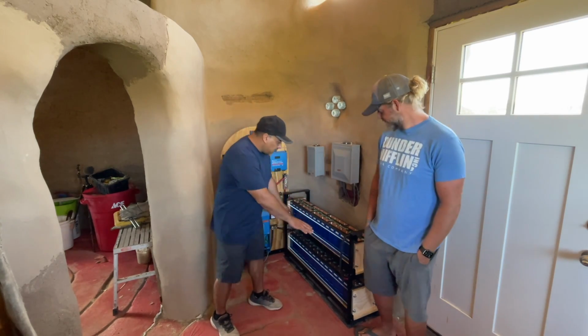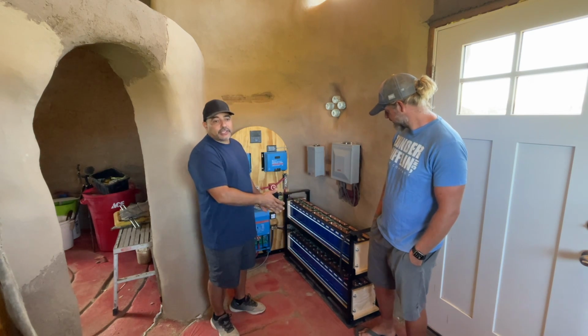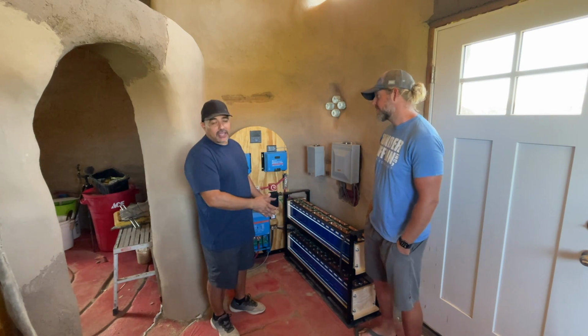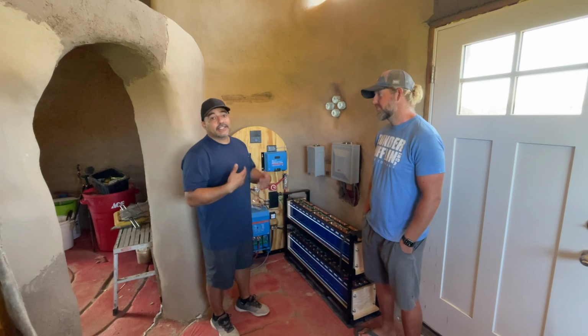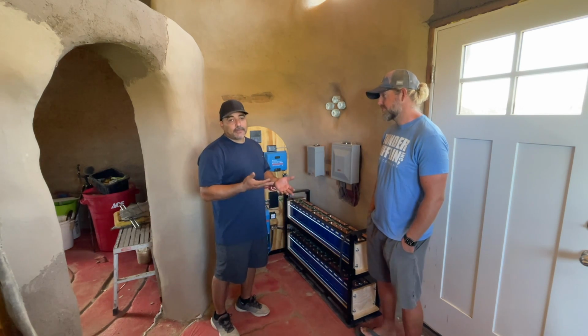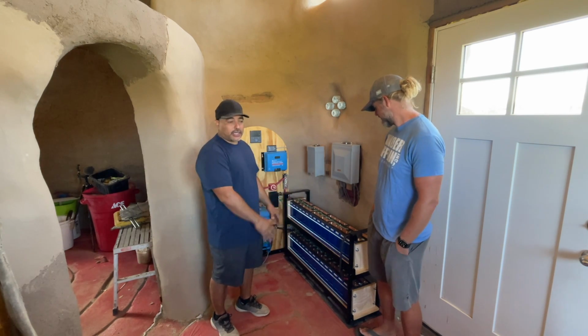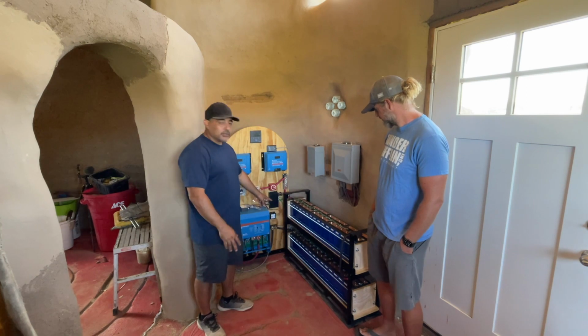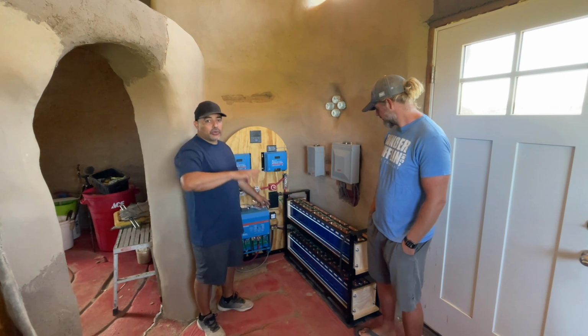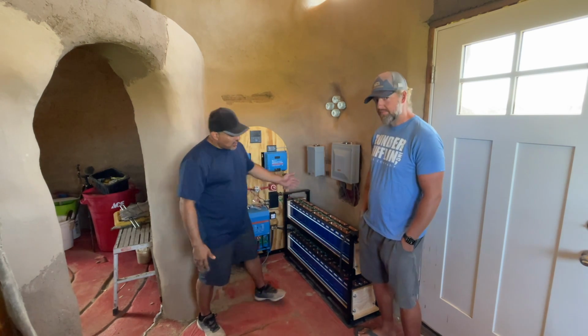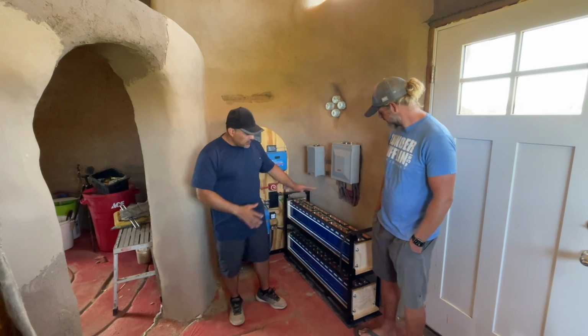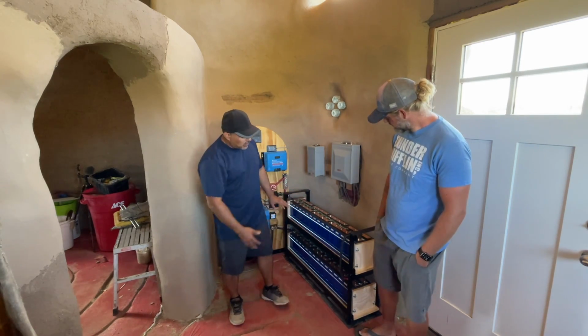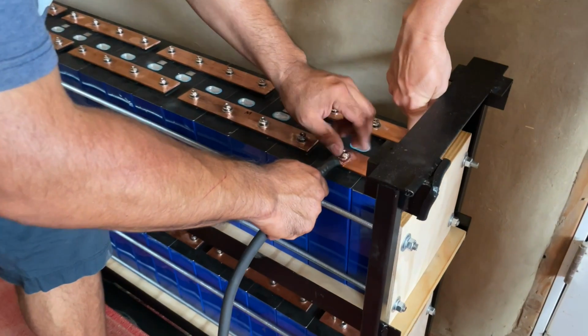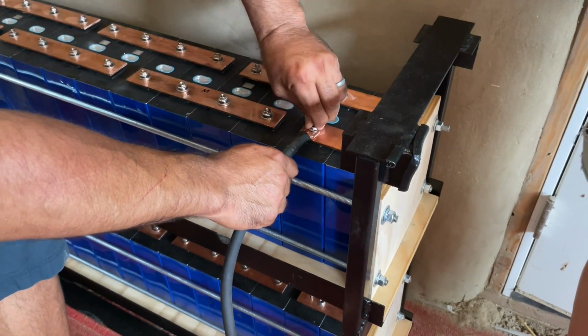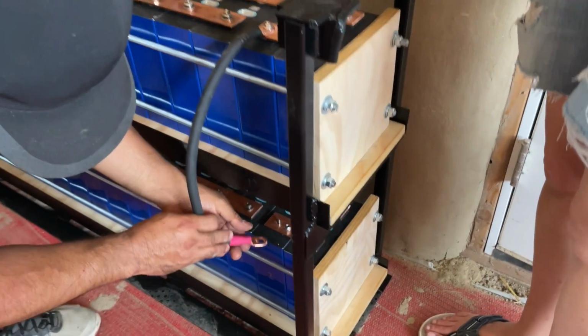There's 32 cells here. It's a 48 volt system, so it's 16 cells in series with 2 in parallel. We paralleled 2, then hooked them in series to 2 more, all the way to 16. We had to do them in 2 rows because of space constraints, and so we tied them together with a big 2-aught cable, which you can see right here.